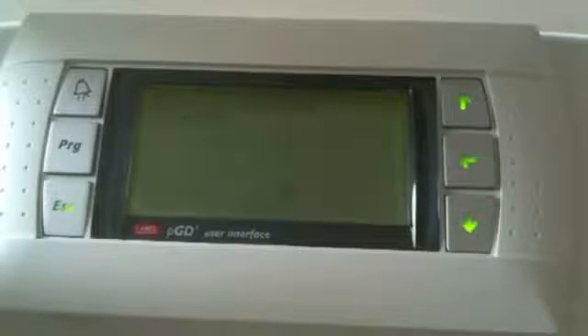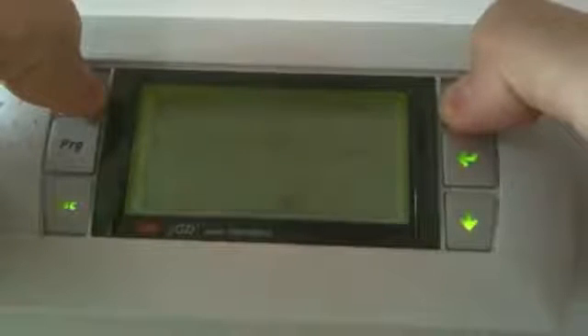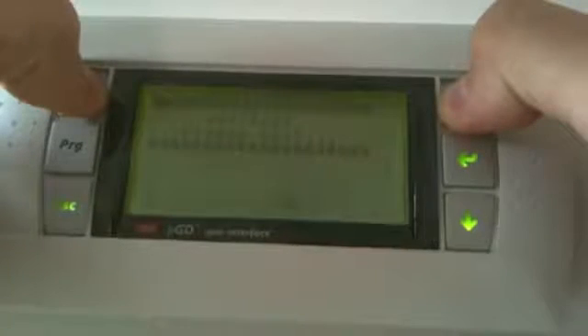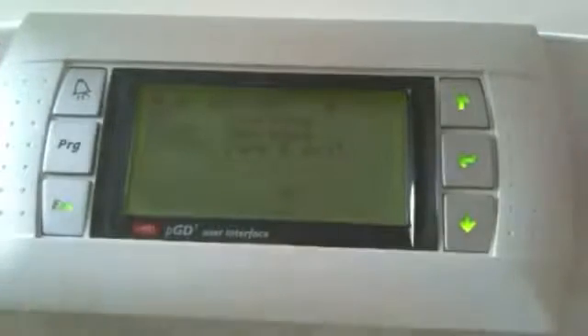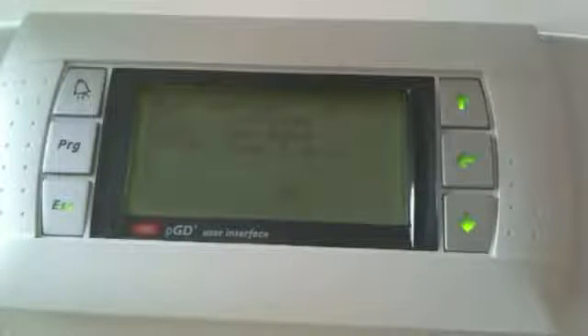Once the address has been set to 00 — just for a temporary period of time — we have to address the controller to 01. To address the controller, we power it off and then back on. During its boot-up procedure, press the alarm bell and the up key together simultaneously for some time. The 'self test, please wait' screen will appear; keep pressing the buttons until the PLAN address screen appears.